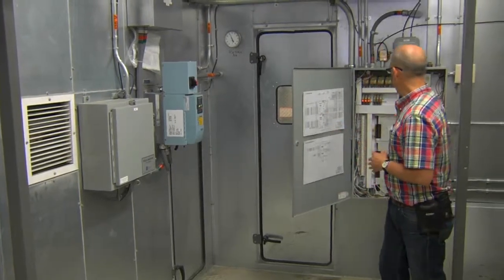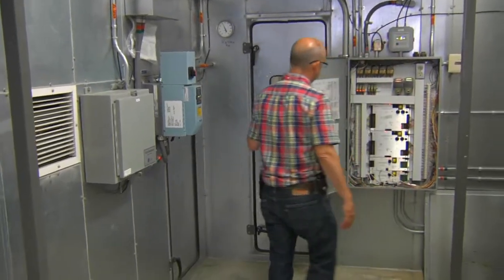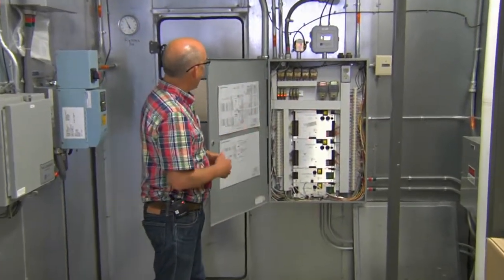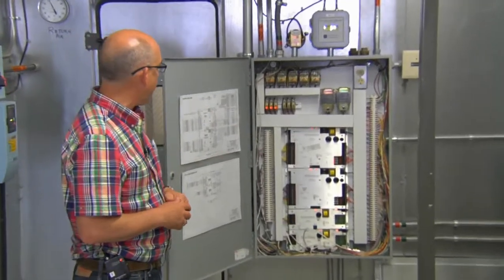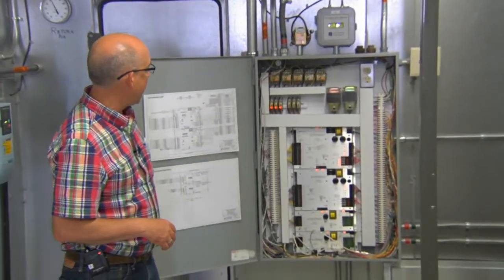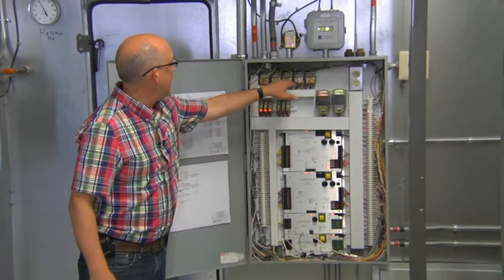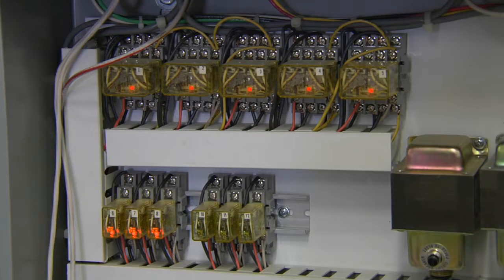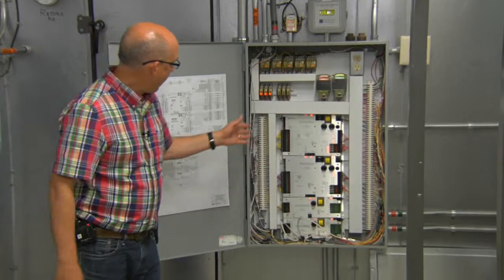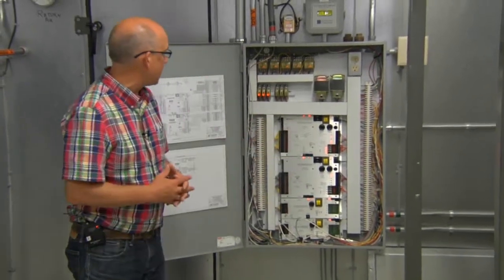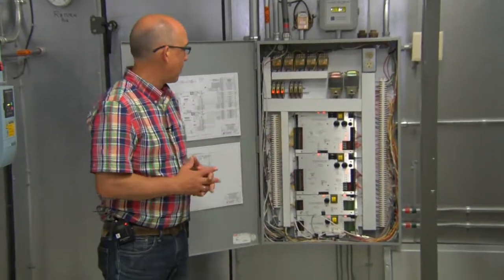Right behind me here is the control panel. And what we want to look at when we're looking at a control panel is we want to make sure that any plug-in relays that you see right here, they're not tipping out of the sockets. These are plug-in socketable relays. You can see the LEDs light up when they're energized. And we look down here, we can see the controllers. This is Automated Logic, real good product.